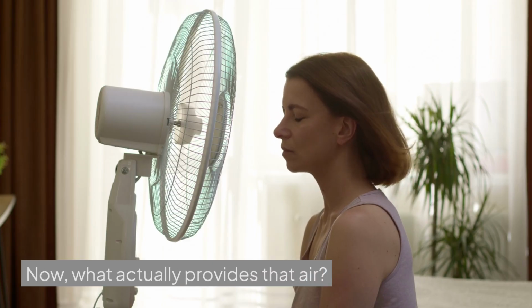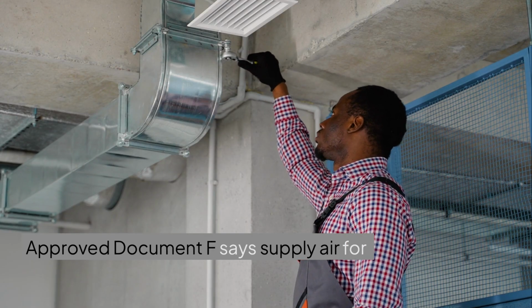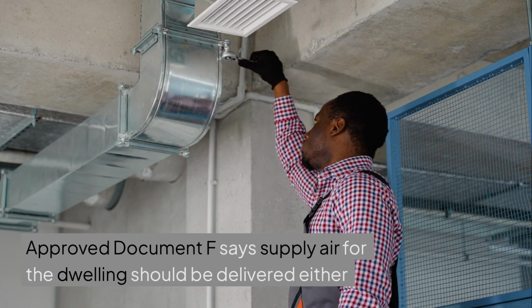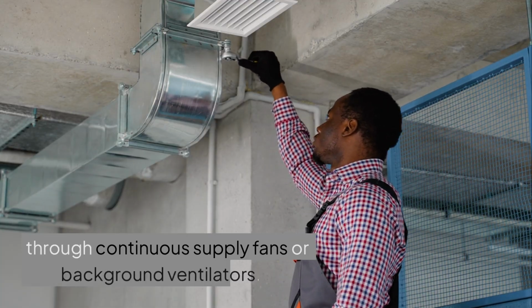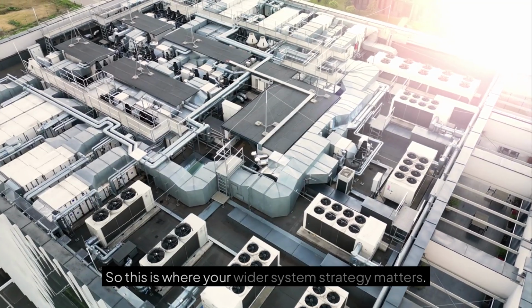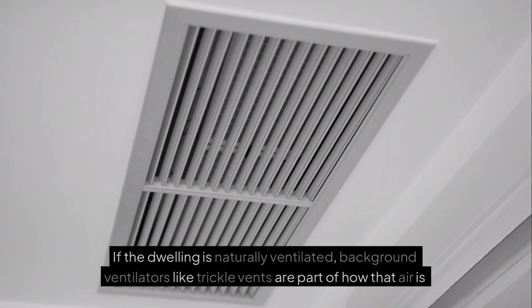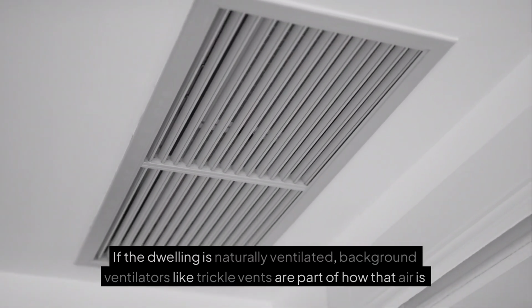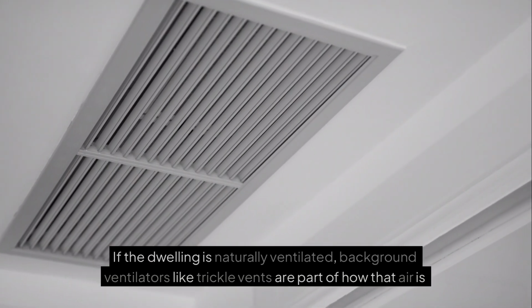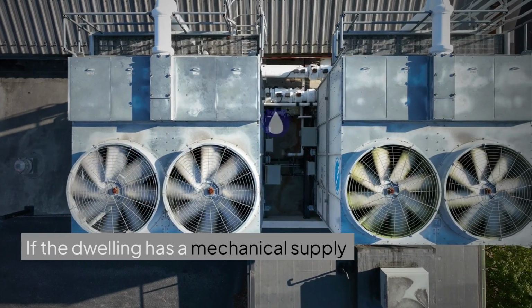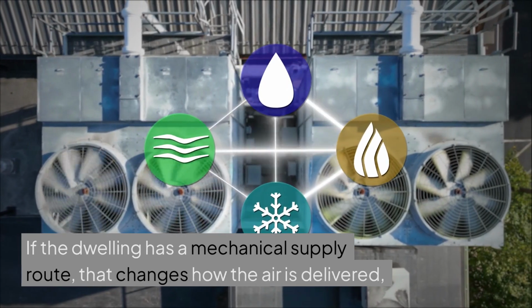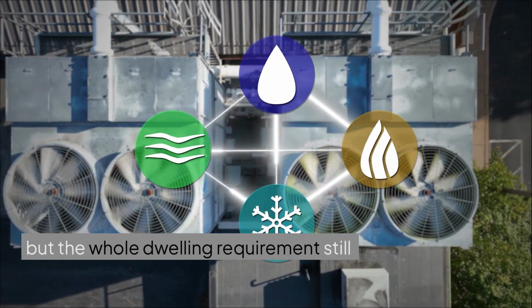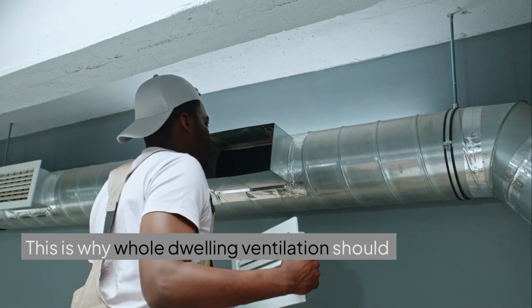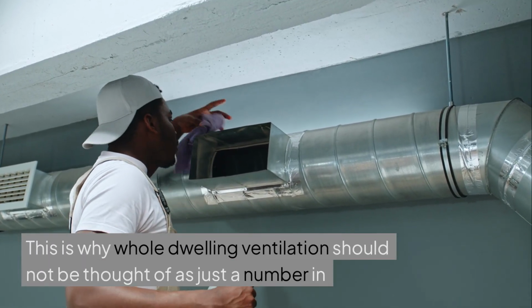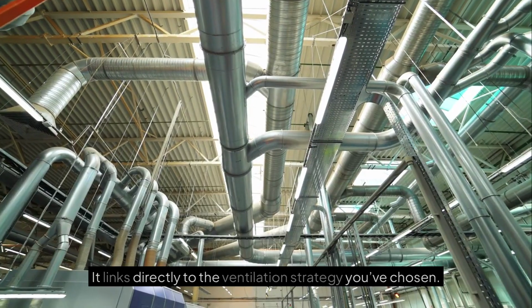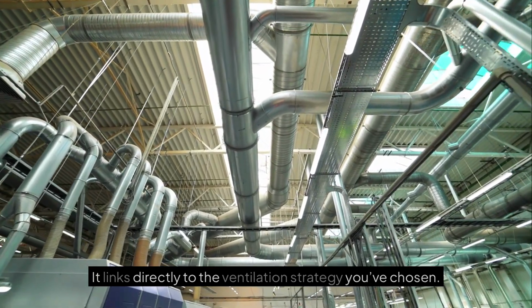Now what actually provides that air? Approved Document F says supply air for the dwelling should be delivered either through continuous supply fans or background ventilators. So this is where your wider system strategy matters. If the dwelling is naturally ventilated, background ventilators, like trickle vents, are part of how that air is provided. If the dwelling has a mechanical supply route, that changes how the air is delivered, but the whole dwelling requirement still exists. This is why whole dwelling ventilation should not be thought of as just a number in isolation. It links directly to the ventilation strategy you've chosen.